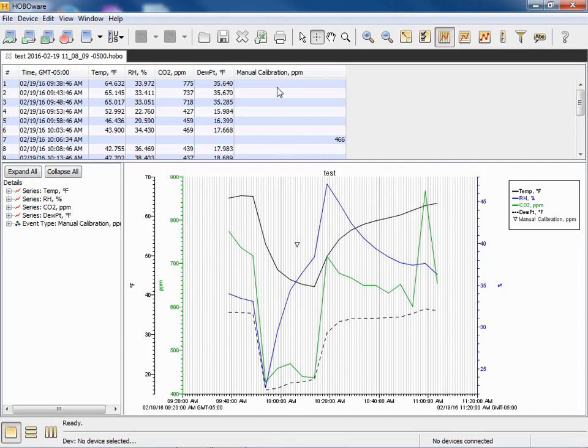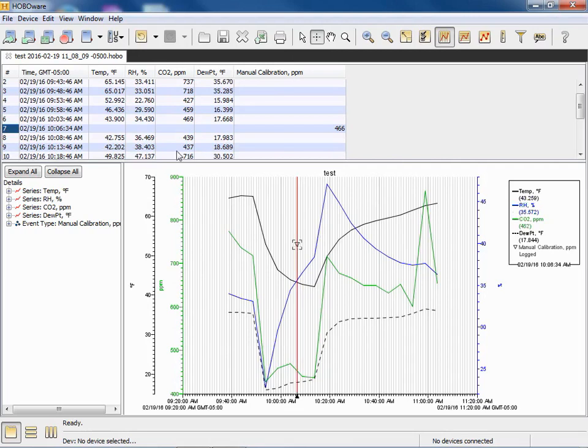Again, we did that using the crosshairs tool. If we click right on that, this is the internal event right here. Takes us right to that point. It was 10:06 a.m. this morning when we did that. And again, this is the manual calibration. Automatic calibration happens 24 hours after launch if a manual calibration doesn't happen before then, and then every 8 days after that.